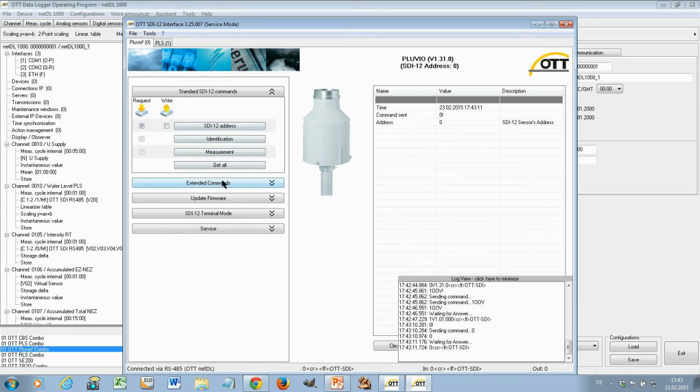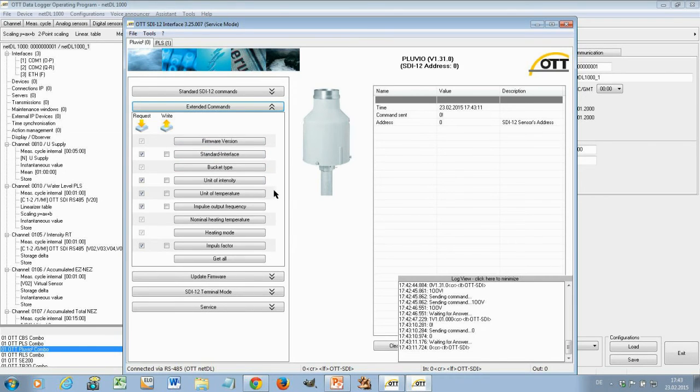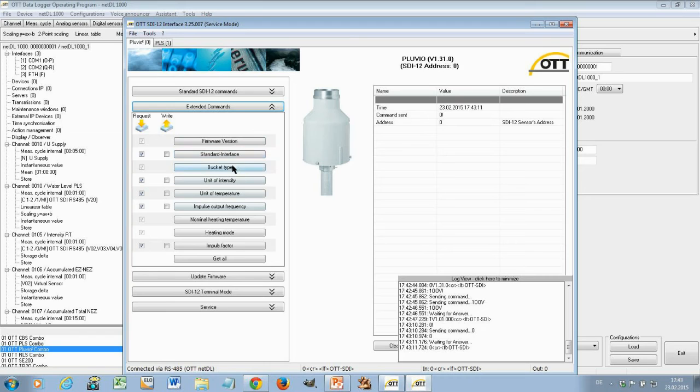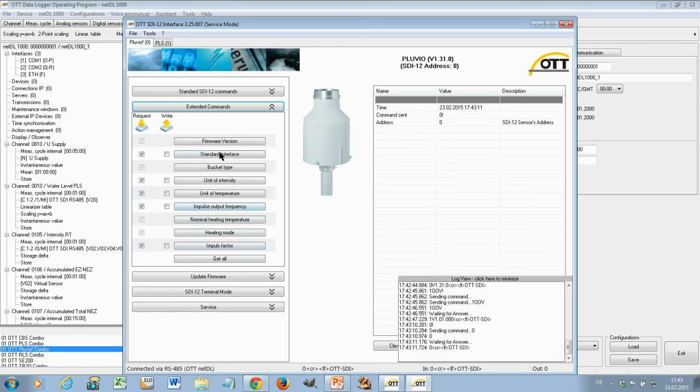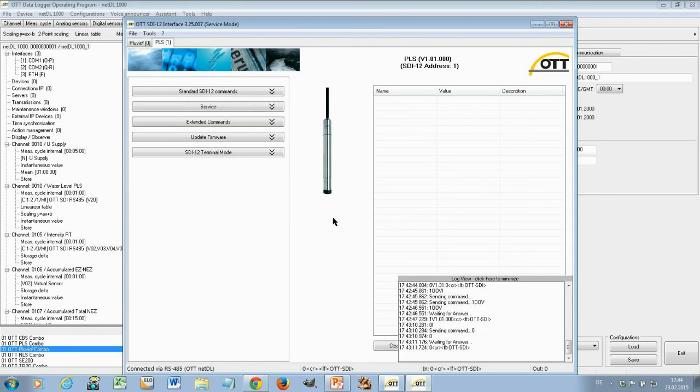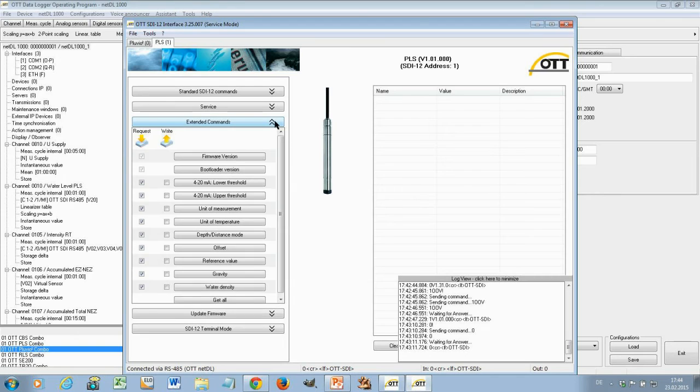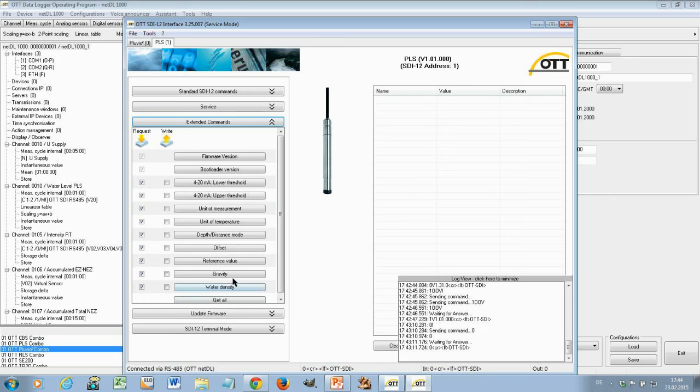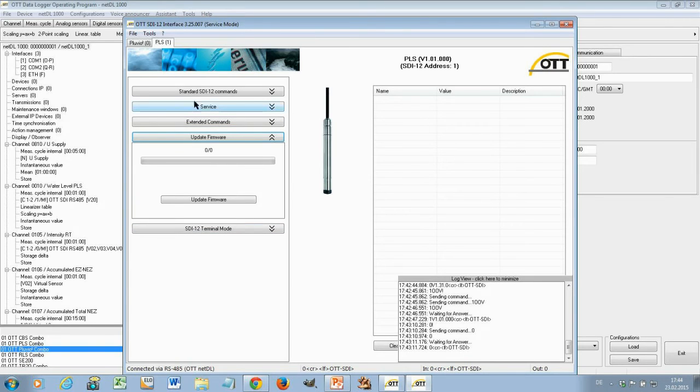These are the standard commands. Then we have the extended commands which are related to the device itself. So now here for the Pluvio. You see here firmware version, standard interfaces, the bucket type, unit of intensity, unit of temperature, impulse output frequency. Those are all Pluvio specific things. And every time you have a checkbox on right you can also change these values. Give you an example on the PLS. Same thing. Standard commands or also extended commands. Now these commands are related to the PLS. For example you can change here the gravity of the device and so on. You can do also here a firmware update of the PLS itself.